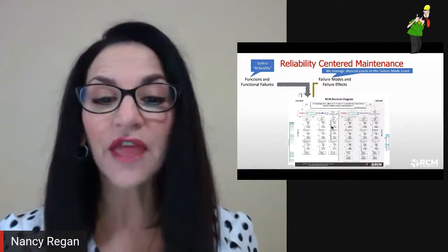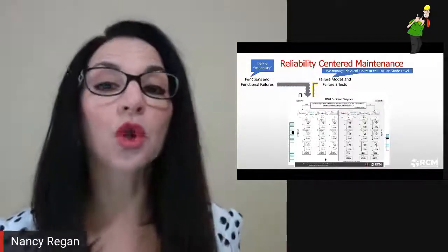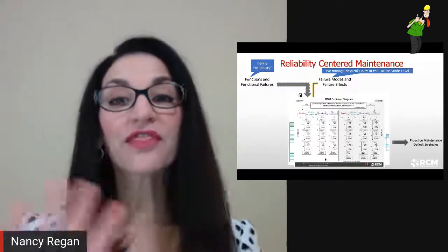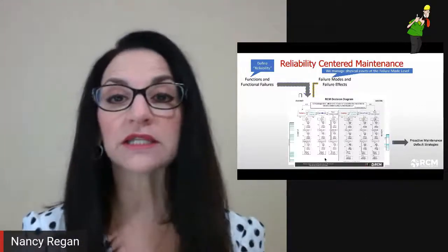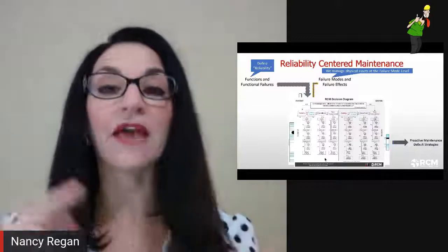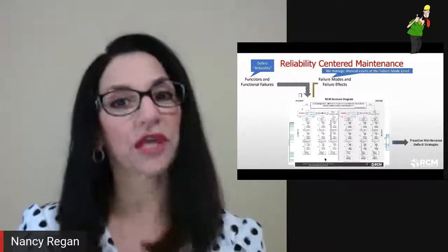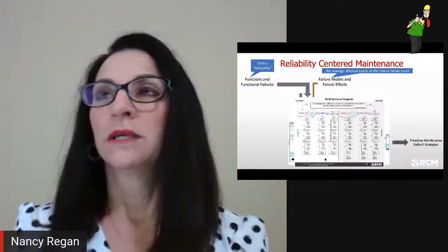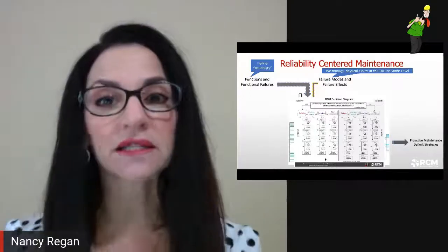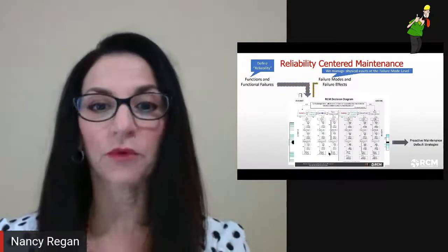We also feed our RCM engine with failure modes and failure effects. We manage physical assets at the failure mode level — in other words, a failure cause — what specifically causes a functional failure. We feed all of this in, put each failure cause through the RCM decision diagram, assess consequences, and we come out with an optimized maintenance program. That's our output, just like power from an engine — proactive, preventive, and condition-based maintenance, plus other default strategies.